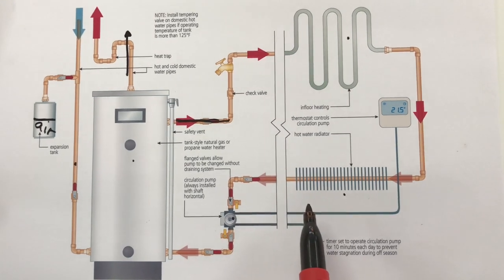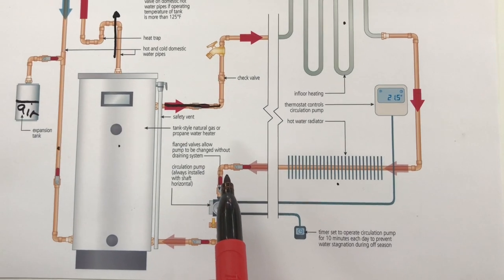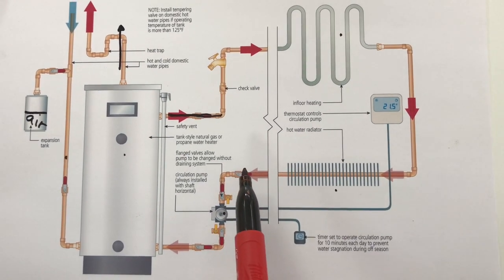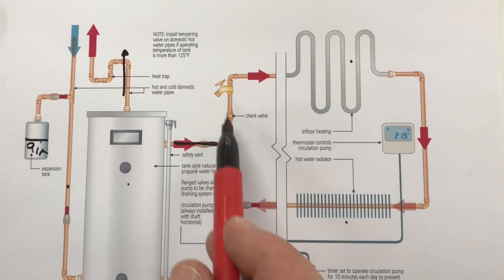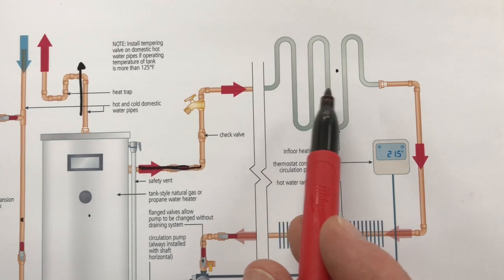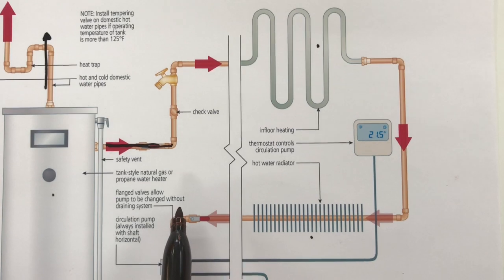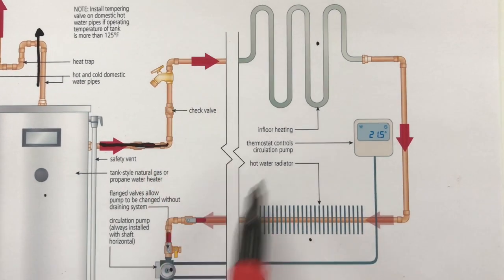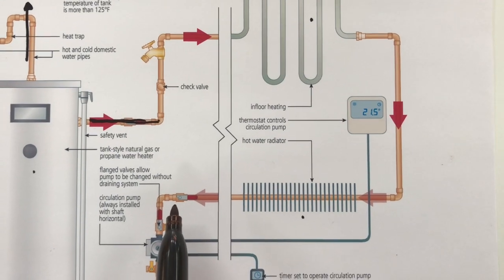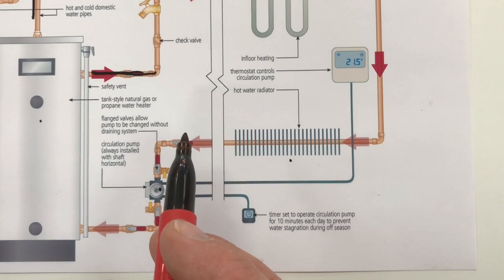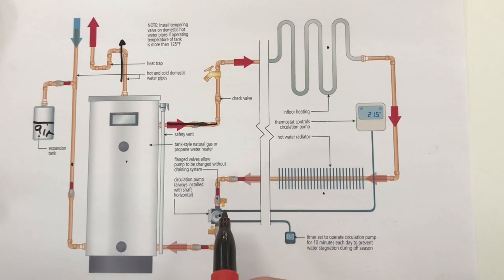Now the simple system is good but it can't be used in all jurisdictions because of a potential problem. And that problem has to do with the fact that in the off season the water that's in the heating side of the system is going to just sit there. It's possible that microbes could grow in there because the water is not circulating for months on end and some jurisdictions do not allow that.